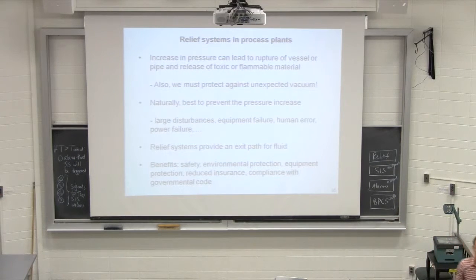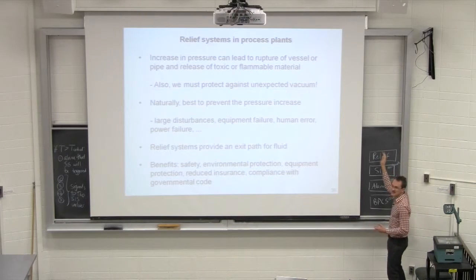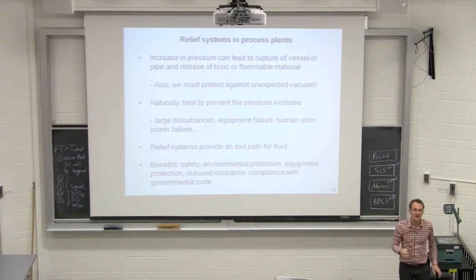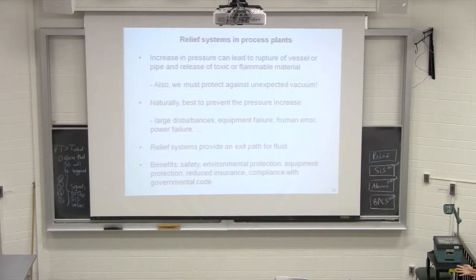As I said in an earlier class, you actually see this in practice. Many companies use their relief system in a bit of a lazy way. But really, you shouldn't ever see your relief system being used. The intention of the relief system is that it isn't going to be used, and when it is used, it should be investigated as a significant safety issue. Remember that phrase that Trevor Kletz used in the BP video? The difference between a near miss and an accident is a very, very fine line. It's just a little bit of difference in the scenario that would have pushed your near miss to be an accident. You can consider the use of relief to be a near miss. It's not something that normally should be used.